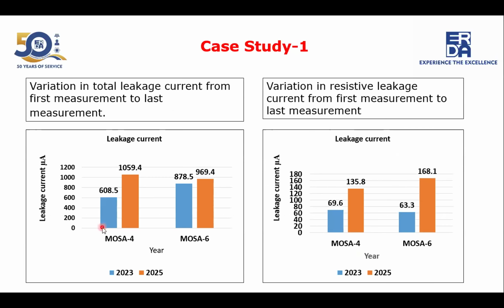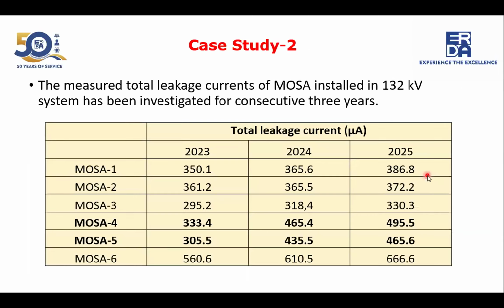These are the comparisons for MOSA 4 and MOSA 6. The total leakage current increased from 600 to 1059 for MOSA 4, and from 878 to 969.4 microampere for MOSA 6. Similarly, the resistive leakage current increased from 69 to 135, and from 63 to 168. By comparing the trend analysis, we can decide whether the lightning arrestor should be replaced or continue in service.